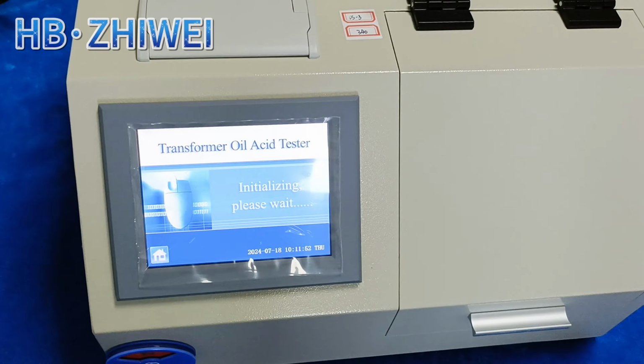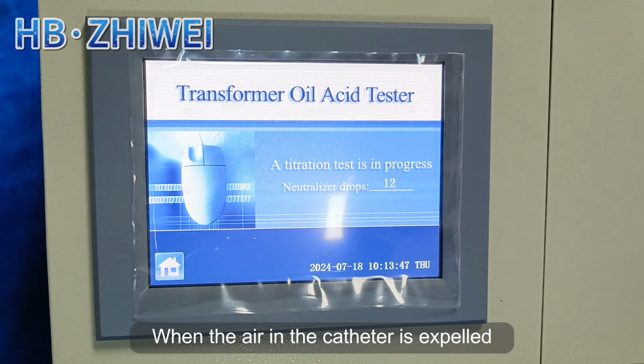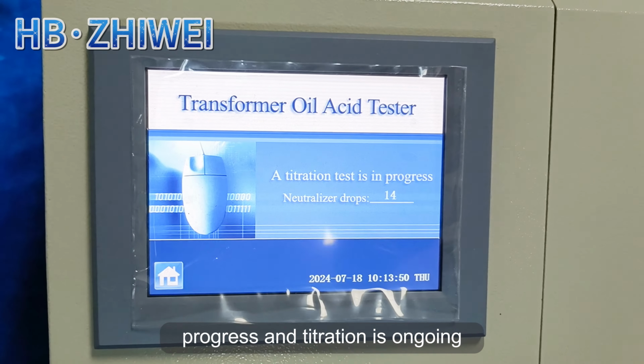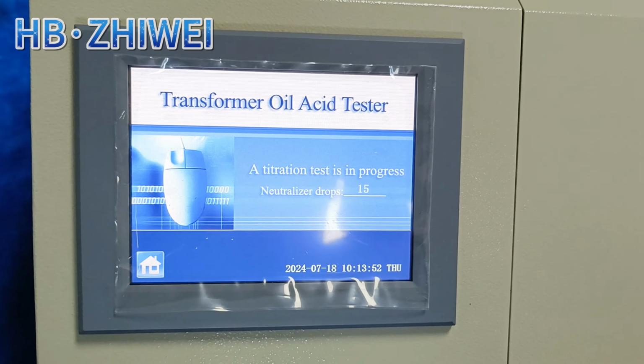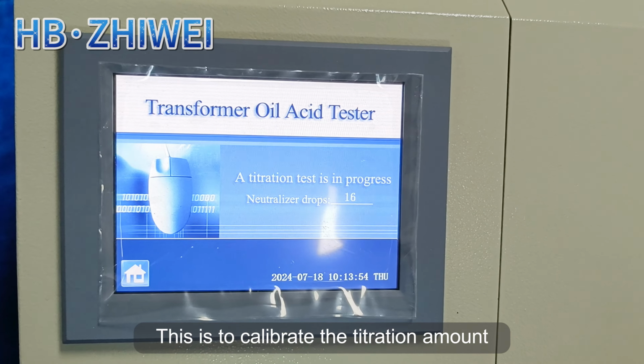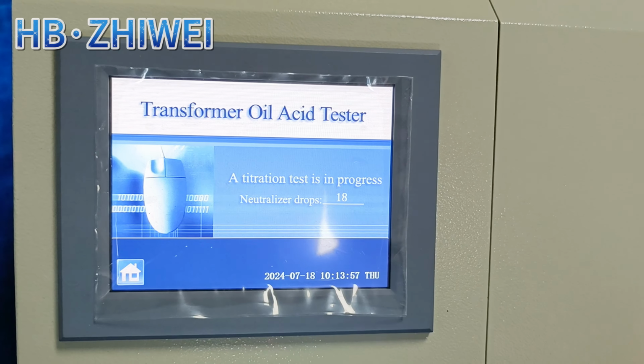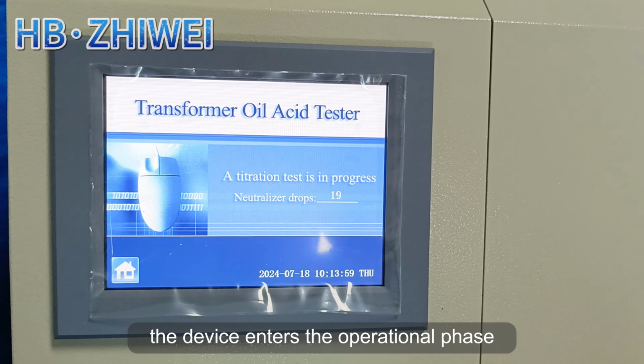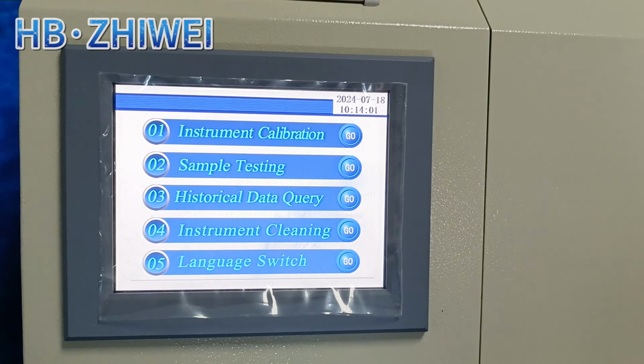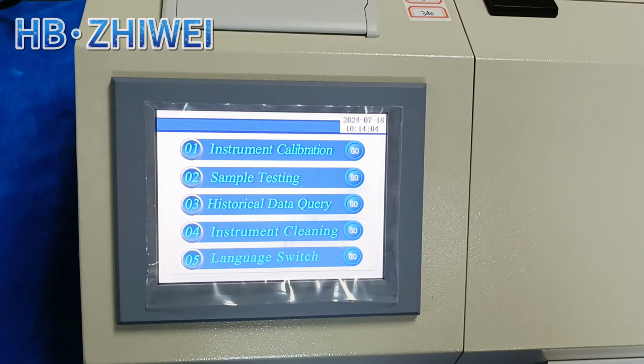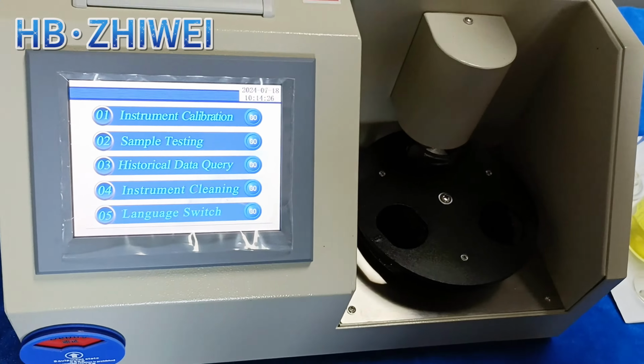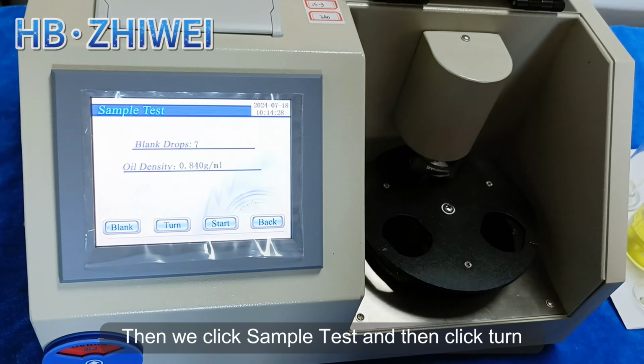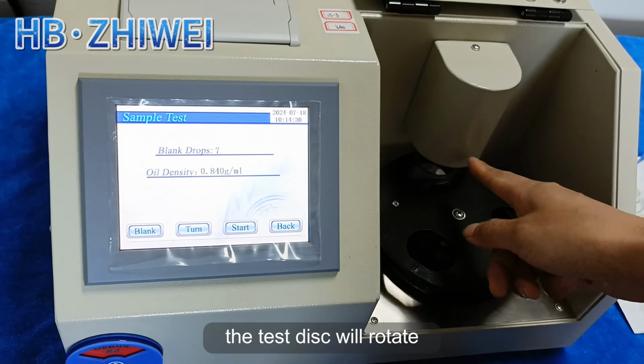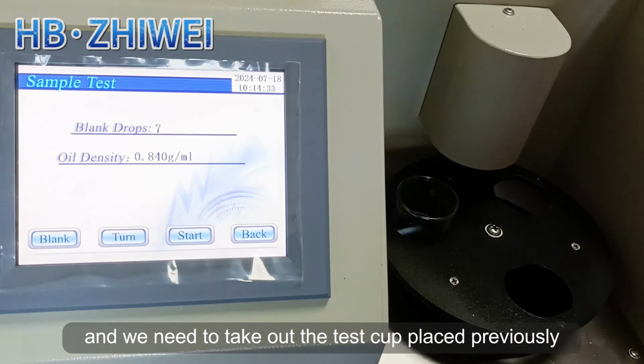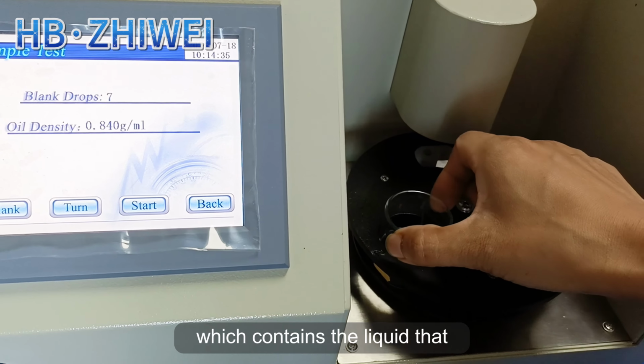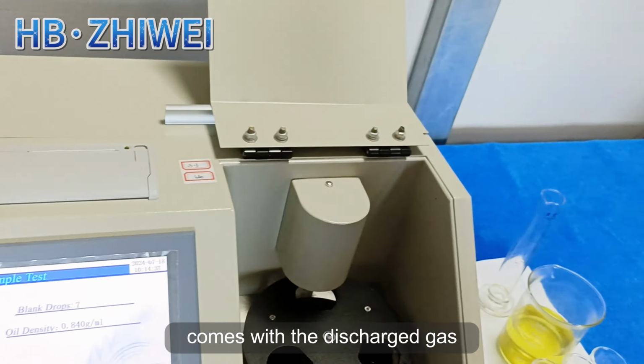Let's fast forward. When the air in the catheter is expelled, the screen will indicate that the device is in progress and titration is ongoing. This is to calibrate the titration amount, which are all programmed steps. When the titration is completed, the device enters the operational phase. Then we click Sample Test and then click Turn. The test disc will rotate, and we need to take out the test cup placed previously, which contains the liquid that comes with the discharged gas.